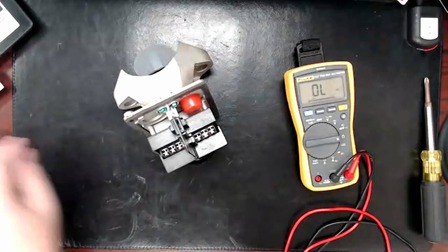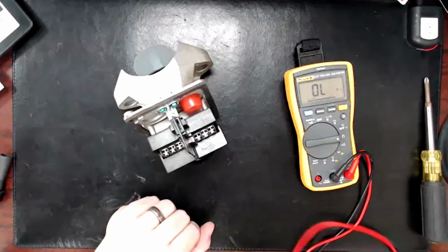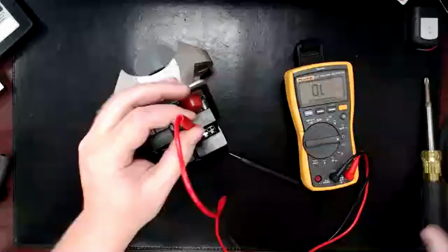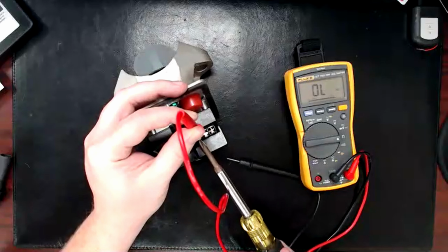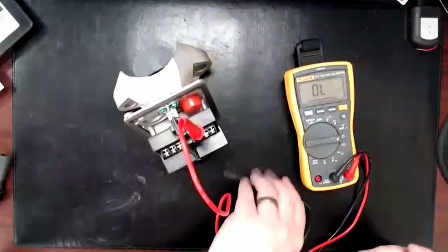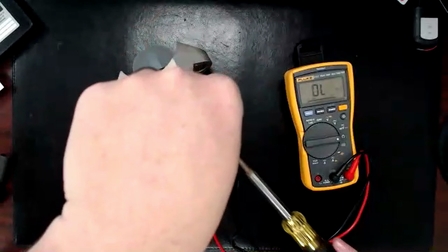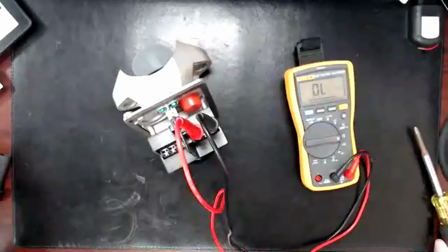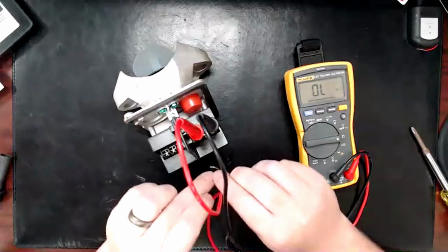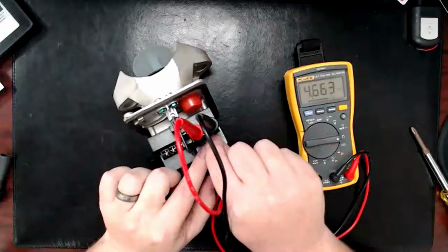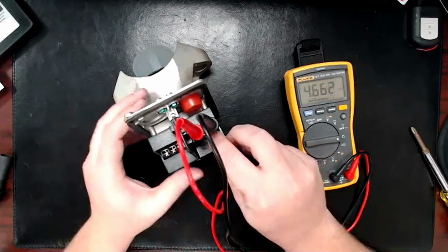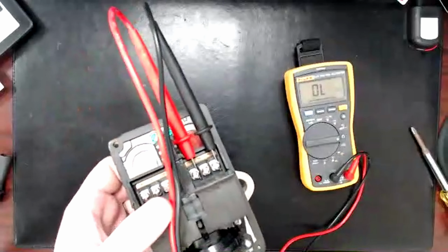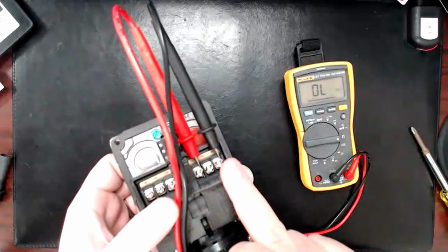So wiring up to supervise this with your meter or with your monitor module works the exact same way. You still use common, which I'm going to put positive meter lead under the common terminal here, and you use normally open. And here, I'll try to hold the resistor across it so you can see there's that 4.6 k ohms. I'll turn it. There's not a good way with my hand. So I have it on that common here and normally open here.